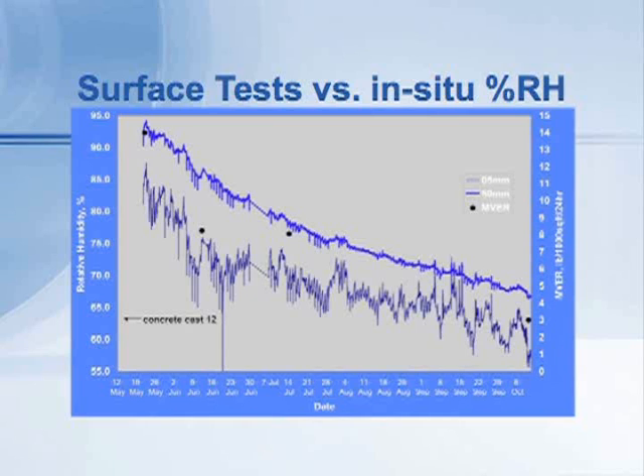Near the surface, you're not getting a true picture of what's happening deeper down. This graph shows why it's so important to put the probe at the proper depth in the slab — generally around 40 percent of the full thickness. The test method was really developed for typical normal floors, four to six inches thick. If you're measuring floors that are much thicker, you may have to make some other decisions. You certainly can put the probes to any depth that you'd like, but typically if you're down two to three inches in the slab, the moisture picture below that depth will be fairly constant. Follow the ASTM F2170 procedure and put the probes at 40 percent of the depth.